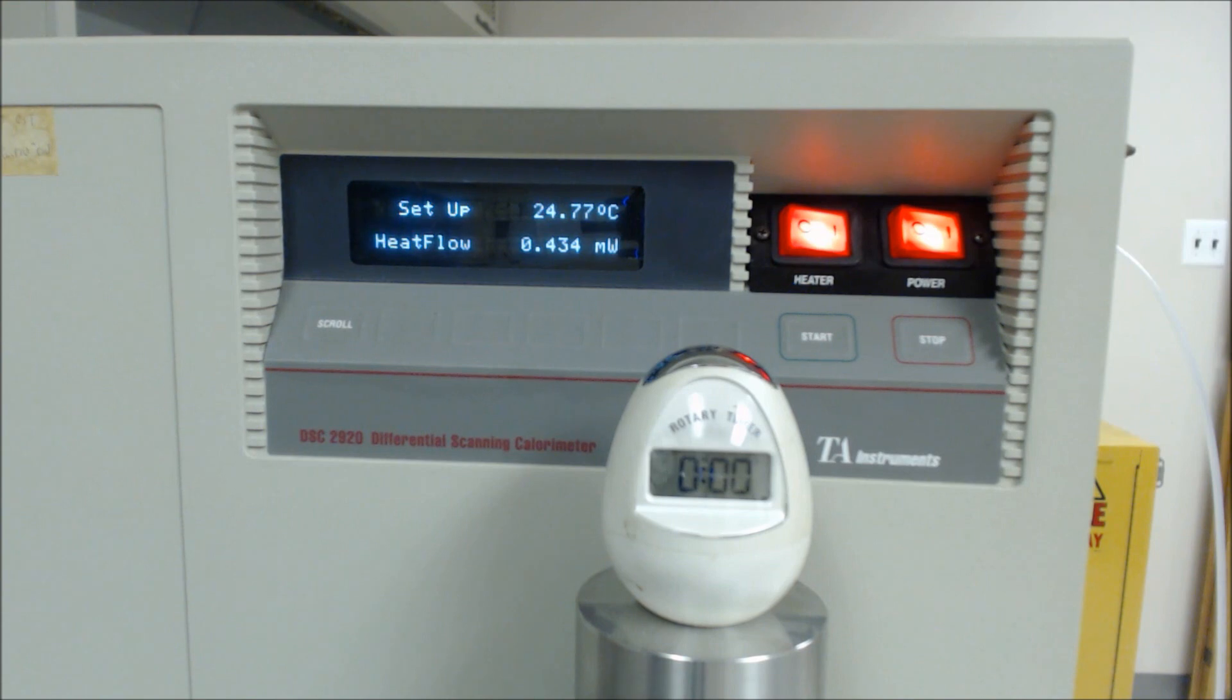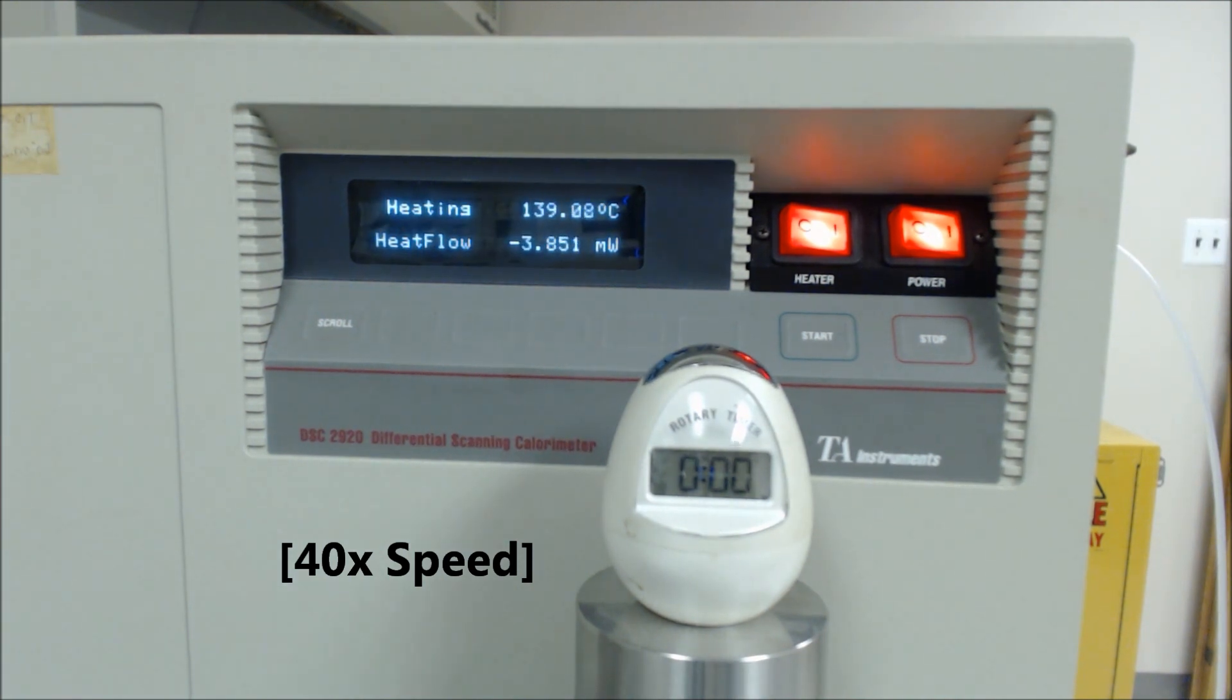The test is now underway as you can see by the red heater light which is just lit up. The first phase of the test is for the DSC cell to ramp its internal temperature up to 200 degrees C, thus melting the plastic. This is done at a rate of 20 degrees C per minute. As you can see by the continuously rising monitor temperature, the cell is doing that now.